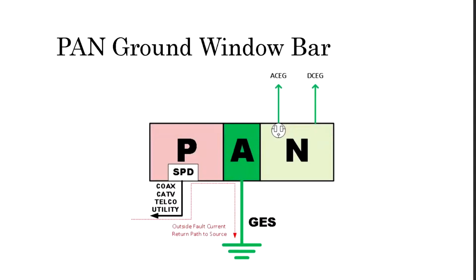Okay, let's take a little deeper look at the PAN ground window bar and how it works. As I noted earlier, we use a ground bar to manage our ground plane, and that's exactly what we're doing here. In order for current to flow, it has to have an entry point and an exit point. Now, the thing with outside surges or outside producers, lightning, the utility, they're not looking for our radio equipment. They're looking for earth right down here. So what we're able to do with the PAN bar is bring the producers into one zone and direct it straight to earth.